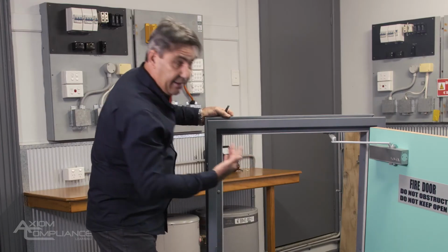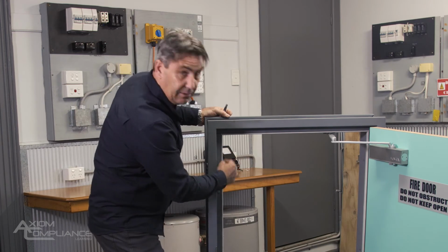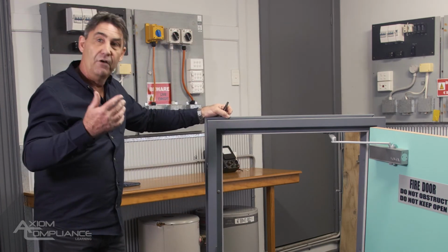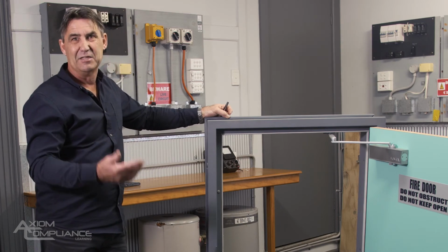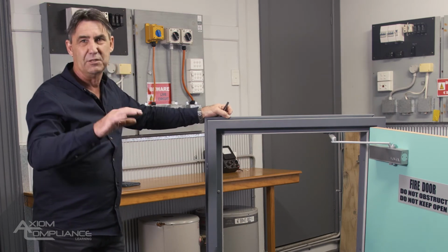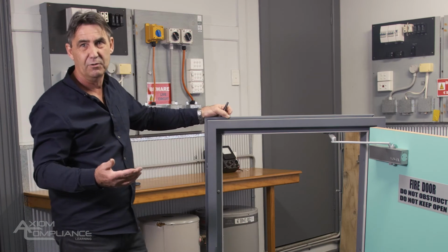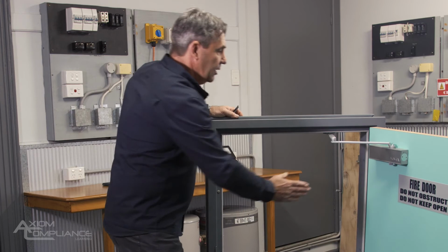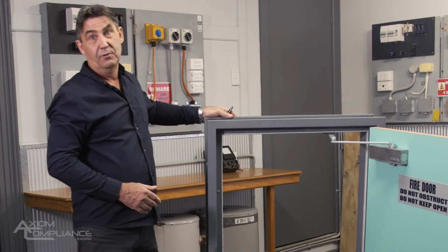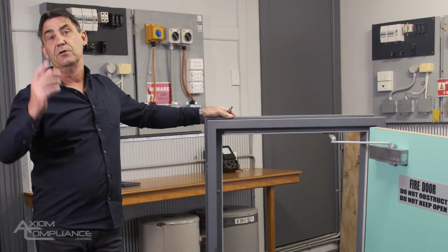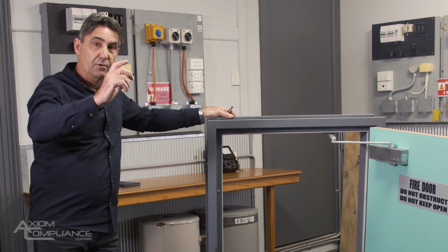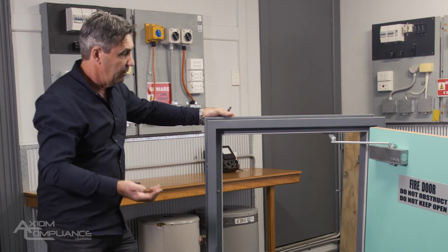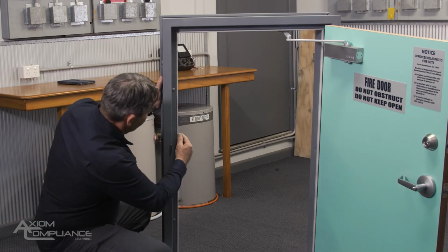And so one of the other inspection points on the list is this seal. So you don't have to have a seal on a fire door. A fire door is not a smoke door. A smoke door is only a smoke door, because that's a part of this subject, fire and smoke doors, but all the same inspections apply, except the smoke door has got a tag telling you it's a smoke door. And when you look in your course notes, you'll see that the smoke door has a separate and different tag to a fire door. So if I have seals, I'm going to inspect the seals.